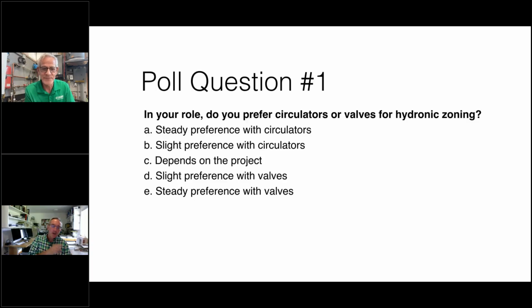But we were talking the other day, Hot Rod, about how in some states there are incentives for ECM circulators, and the circulators after the incentive are almost free. They're very low cost. So that kind of skews the market a little bit, in the sense that why would you pay X dollars for a zone valve when you have a subsidized circulator and you're getting it for $10, let's say. You still have to buy the isolation valves, but I guess that's a cheaper option than a zone valve. Well, that's a good point too.